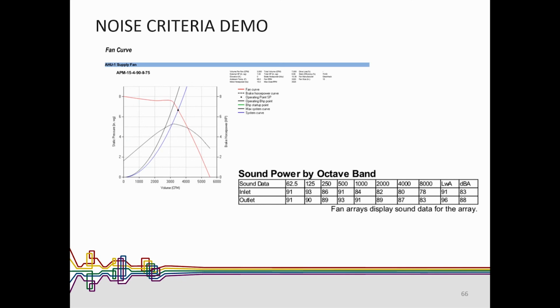So basically when doing a noise criteria calculation for a room, we start out with the equipment making the noise, like a rooftop or air handling unit. This happens to be an air handling unit shop drawing from one of our jobs. You can see we have octave band information, only from 62 up to 8,000. Then we have the power, sound power which is LWA, and DBA. Then we have each octave band by the inlet condition and the outlet condition, because sometimes it makes a difference which way the airflow is going.